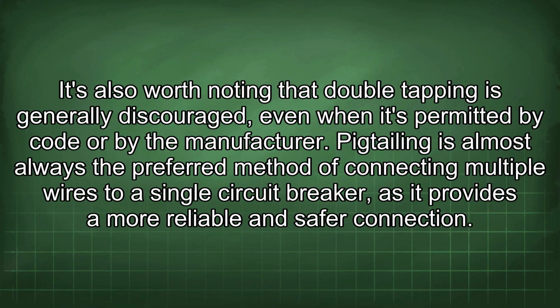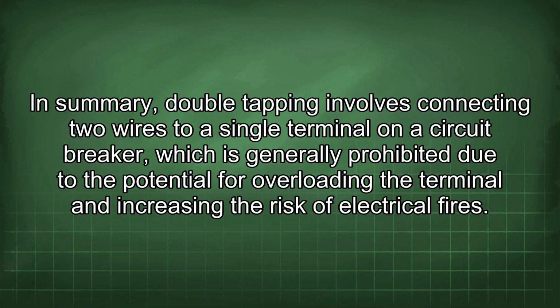It's also worth noting that double tapping is generally discouraged, even when it's permitted by code or by the manufacturer. Pigtailing is almost always the preferred method of connecting multiple wires to a single circuit breaker, as it provides a more reliable and safer connection. In summary, double tapping involves connecting two wires to a single terminal on a circuit breaker, which is generally prohibited due to the potential for overloading the terminal and increasing the risk of electrical fires.